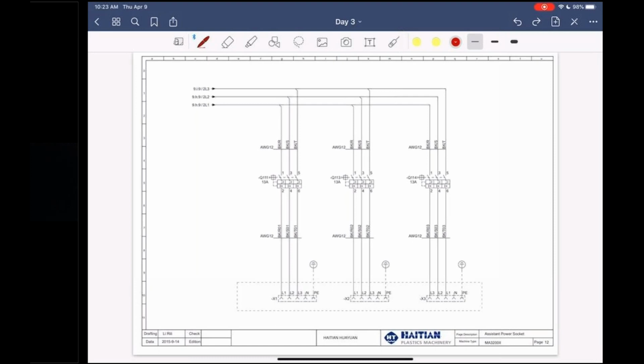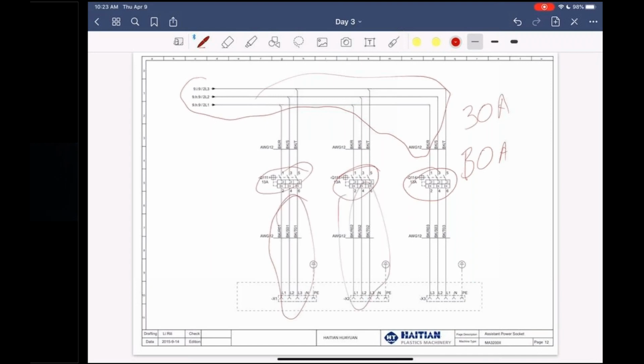Yeah. What I do is, if I'm going to a show, I take these sockets, because sometimes I'll run a chiller. Chiller will probably be 30 amps, and I'll put on a thermolator, or maybe a hot runner box, and the hot runner box may be 30 amps. And so what I do is I change the wires. I'll just take these wires all out, and I'll put a bigger breaker in here. And I'll change all of these wires out, and I'll just run these wires right to the side of the machine rail, where I'll put the outlets right on the machine rail.